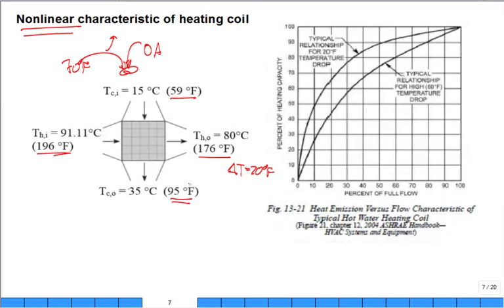So you design this to work on the really cold days, but most days are not really cold. So you modulate it, you throttle back. One way to throttle it, it's easy to control, is put a valve on the water flow and just reduce the water flow. So you design everything and you have it 100% on the coldest day, but you reduce the water flow to 50%. Hot water flow goes to 50% or 30% or 20%.